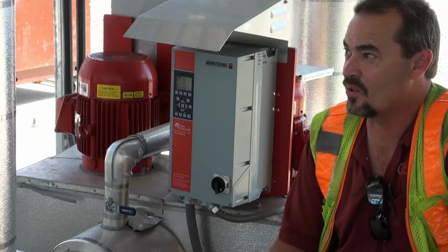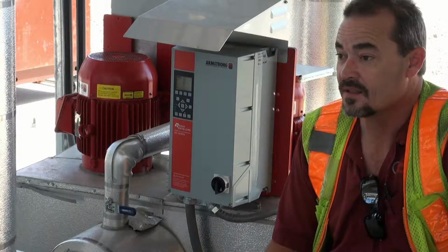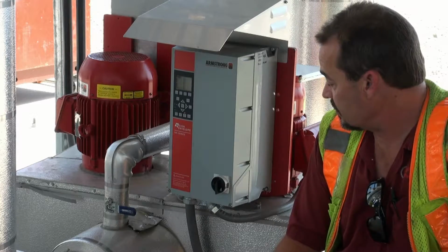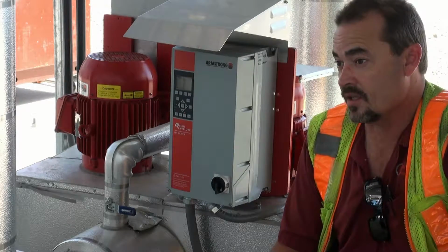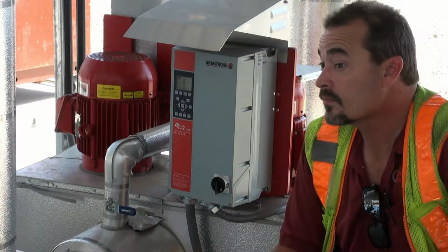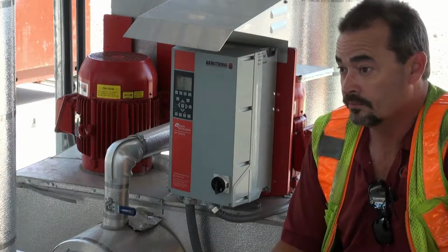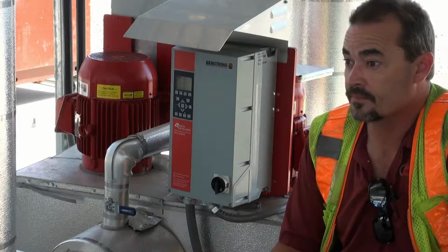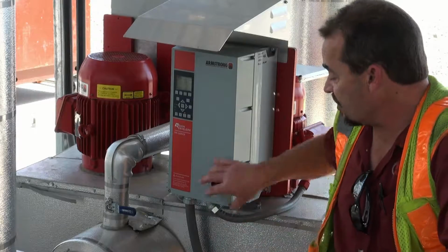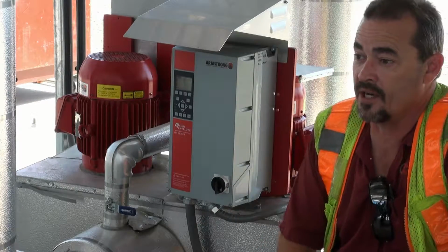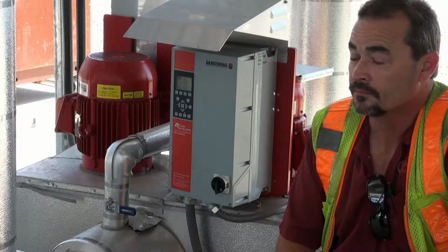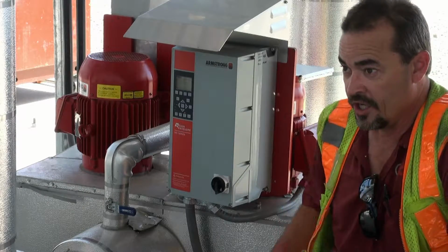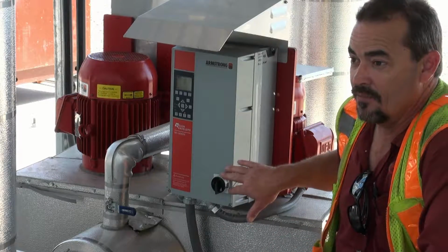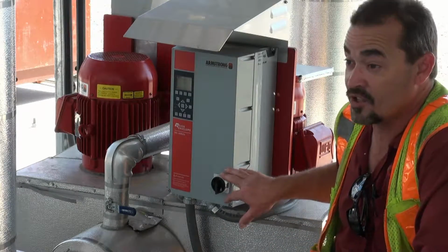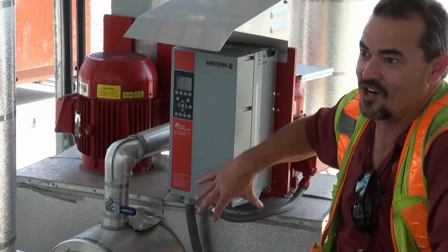A lot of times it's what you get used to using too. It makes it simple. When that cover comes off, the disconnect has to be off. Is there a way to defeat that? No, it has to go off. This one does not have a defeating mechanism at all. And remember, if you do turn it on with the cover off, you have to turn it back off to get the cover back on.